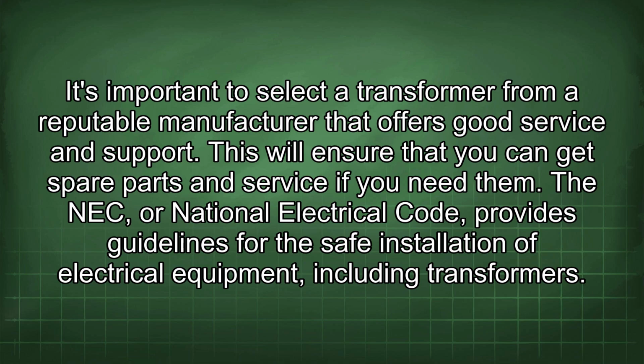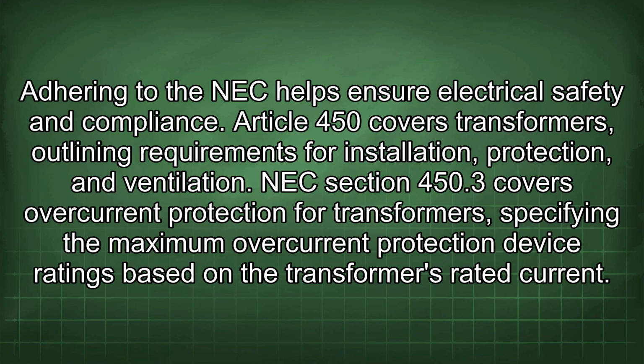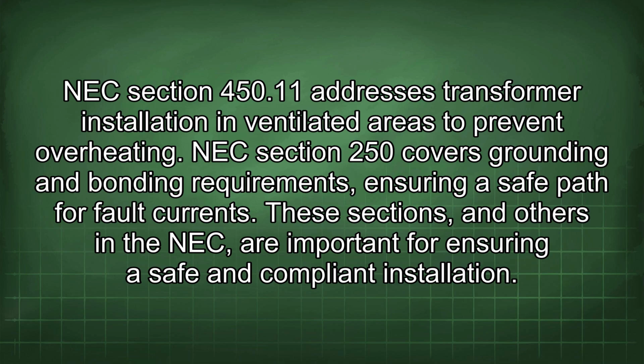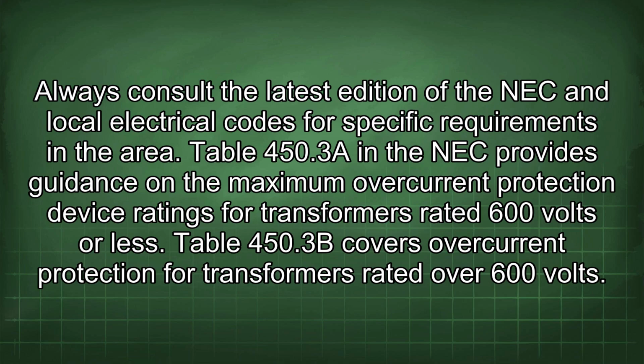The NEC, or National Electrical Code, provides guidelines for the safe installation of electrical equipment, including transformers. Adhering to the NEC helps ensure electrical safety and compliance. Article 450 covers transformers, outlining requirements for installation, protection, and ventilation. NEC Section 450.3 covers overcurrent protection for transformers, specifying the maximum overcurrent protection device ratings based on the transformer's rated current. NEC Section 450.11 addresses transformer installation in ventilated areas to prevent overheating. NEC Section 250 covers grounding and bonding requirements, ensuring a safe path for fault currents. These sections, and others in the NEC, are important for ensuring a safe and compliant installation. Always consult the latest edition of the NEC and local electrical codes for specific requirements in the area.